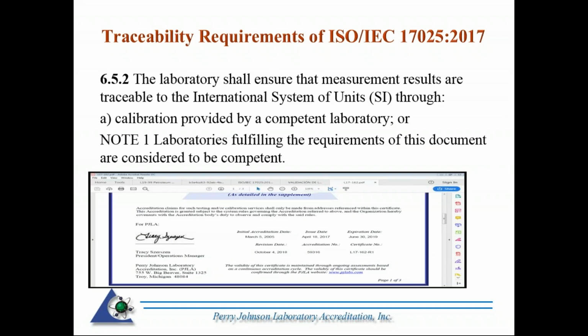Okay, 6.5.2, the laboratory shall ensure that measurement results are traceable to the International System of Units, the SI, through, A, calibration provided by a competent laboratory. So it does not state accredited there, it states competent. Again, we're going to look at the Annex A, we're going to look at PL2, which further clarifies what goes into determining a competent lab. One sure way of assuring that you're going to a competent lab is through accreditation.